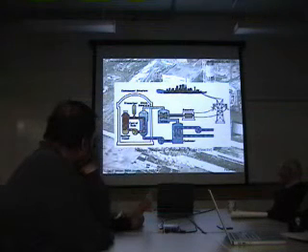What actually led up to it, they realized there were some issues with their design of reactor, and they performed some tests on what would happen in low power situations in case they didn't have enough power to run these pumps that are pumping the water. They found this on a couple of other reactors in that same facility, that they had issues with those when they tested them. They'd done the tests, they completed them, but the tests still came back with bad results, that they needed to make some improvements. So they made improvements to the generator system that would kick in to continue to power the pumps in case of power failure.